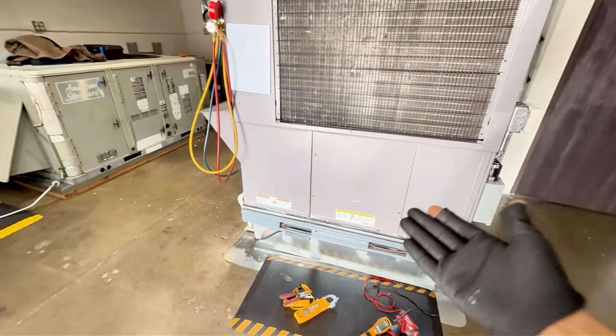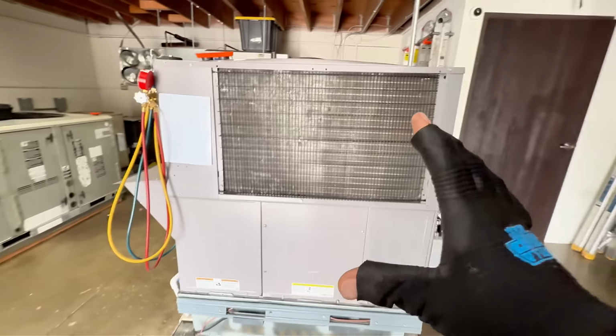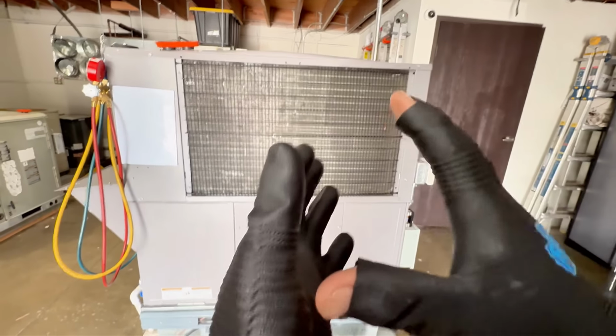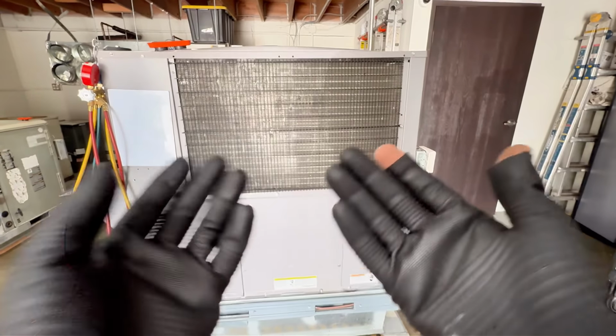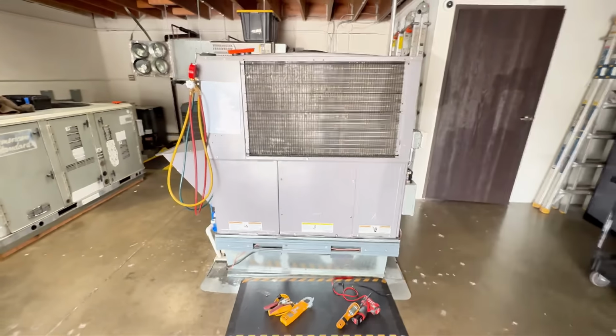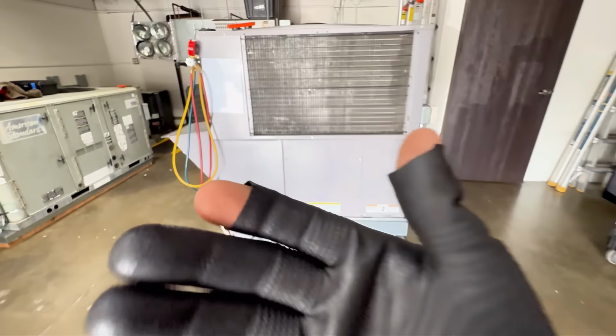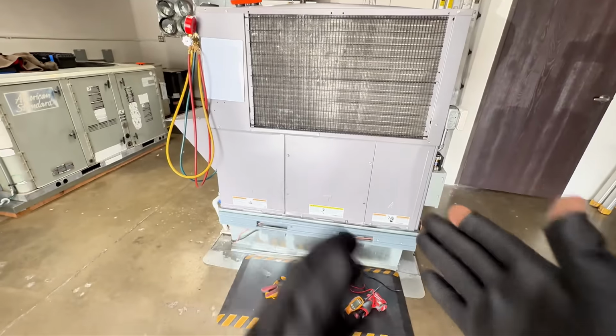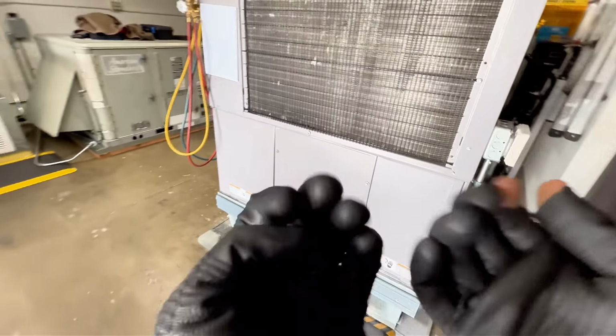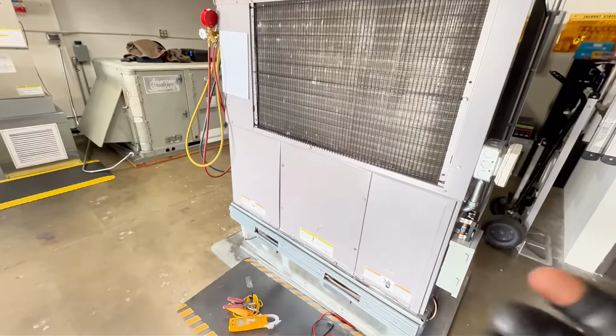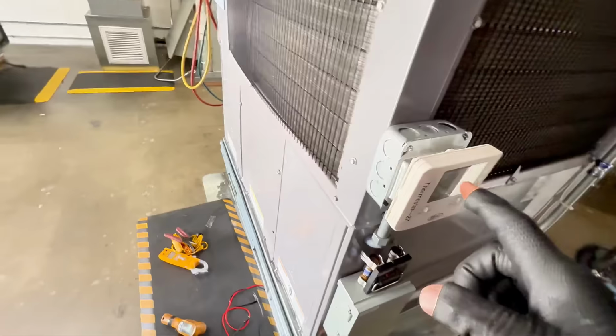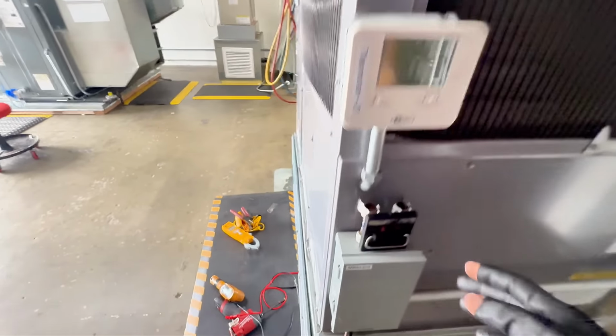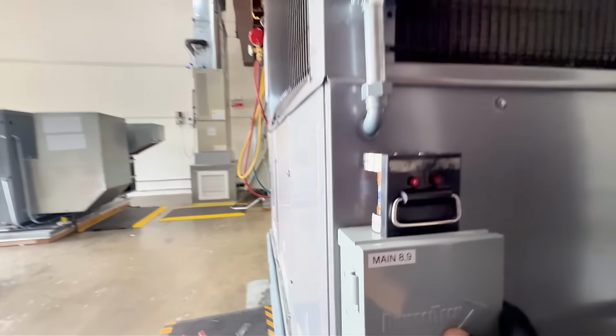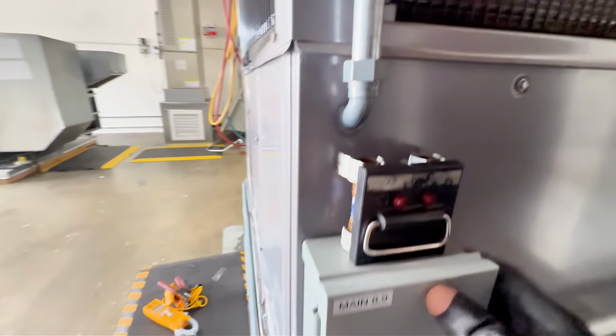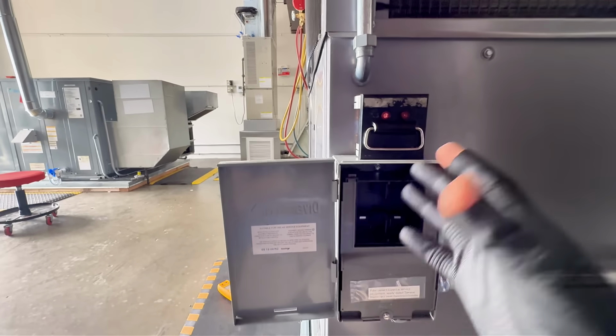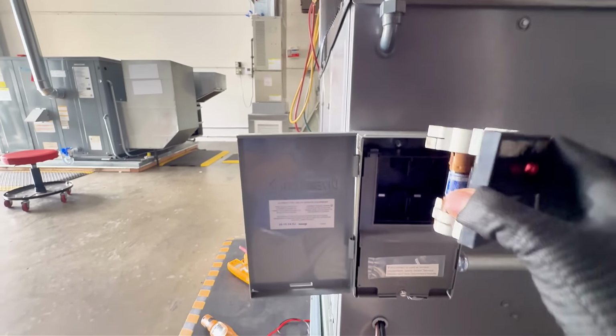Obviously, this is a package unit, so we would be focusing more on the thermostat at their house. This would be up on the roof, or if it's a split system, it could be on the side of the house. But now that we've talked, and now we're in front of the unit, the approach is, at least for myself, everyone's going to have a different approach, start off with the low voltage, start off with the thermostat. So in this case, let's see, we do have the disconnect pulled out. I don't know if he pulled it out for a reason. I am going to go ahead and put that back.